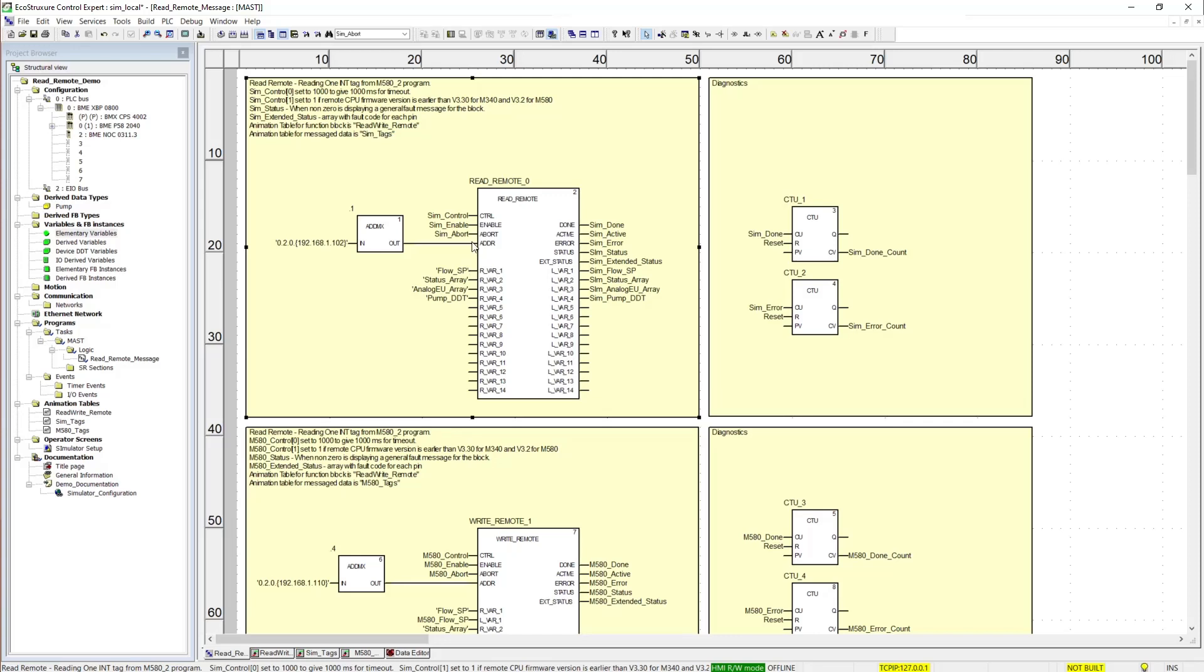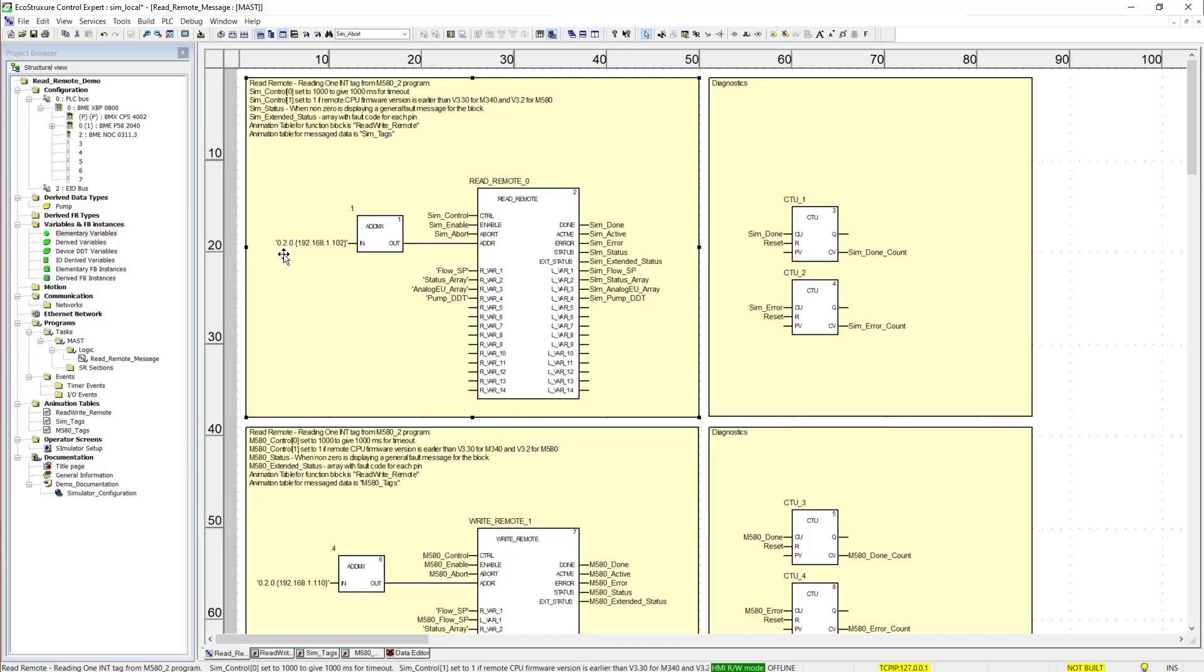We have the ADDR pin. This is connected to an ADDM or an ADDMX function block. The difference is whether using an M340 or an M580. For an M580 you designate the rack, slot, channel and then the PLC IP address you're talking to. On an M340 this would be your Ethernet channel which is Ethernet underscore 1 by default, and then the IP address of the PLC you're talking to.